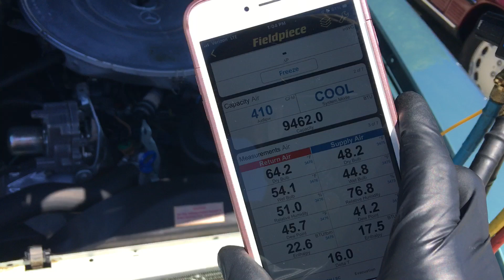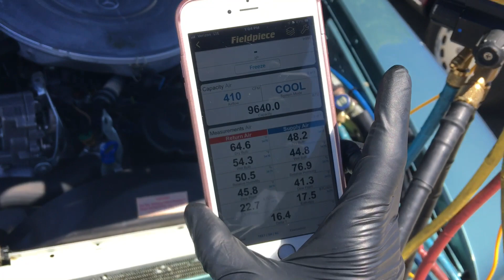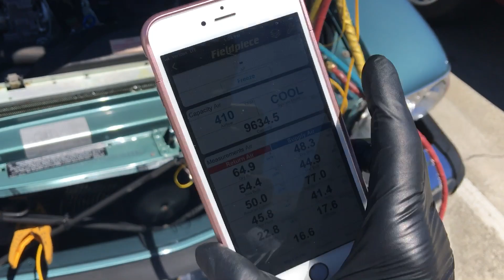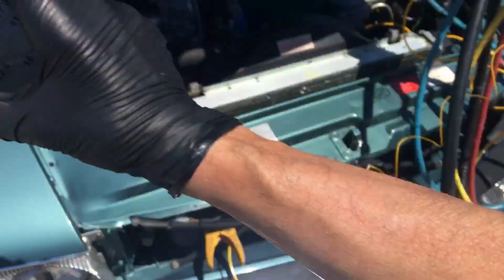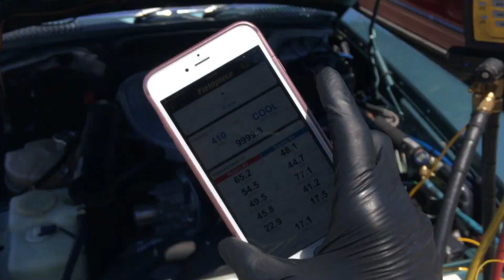And yes, it looks somewhat decent at 48 degrees, and it did go down to 43 degrees, but the ambient air temperature is only 66 degrees, and the sun, judging by my skin, is not very strong today. There's a few clouds up in the sky, and even though it's in the sun, the heat load is not stupendous. So we're starving. I could hear the compressor laboring.